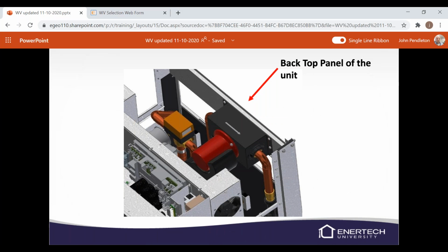This is the top of the unit looking down. You can see there's a load pump. There's a door on the back side that you can kind of access it, but if you have to replace it, you're going to have to pull the top off the unit. So make sure we've got some clearance above the unit as well, so we can get in there and work on it if need be. Next to the load pump, that little orange box, that's your three-way valve for shifting from domestic hot water to your hydronic load water.